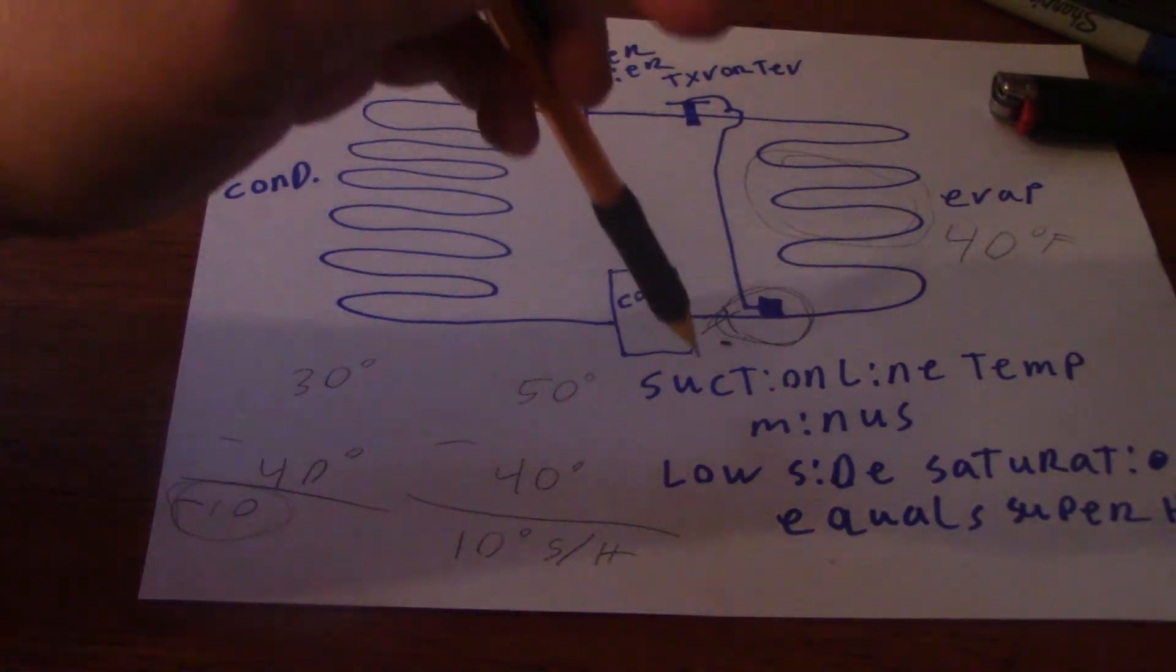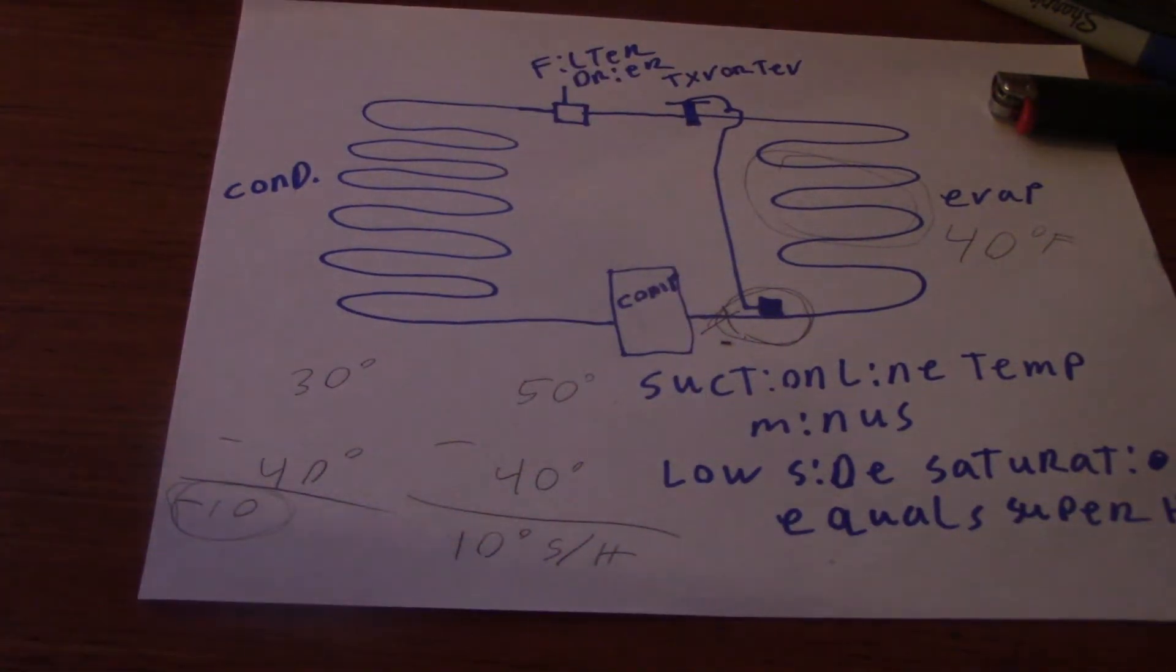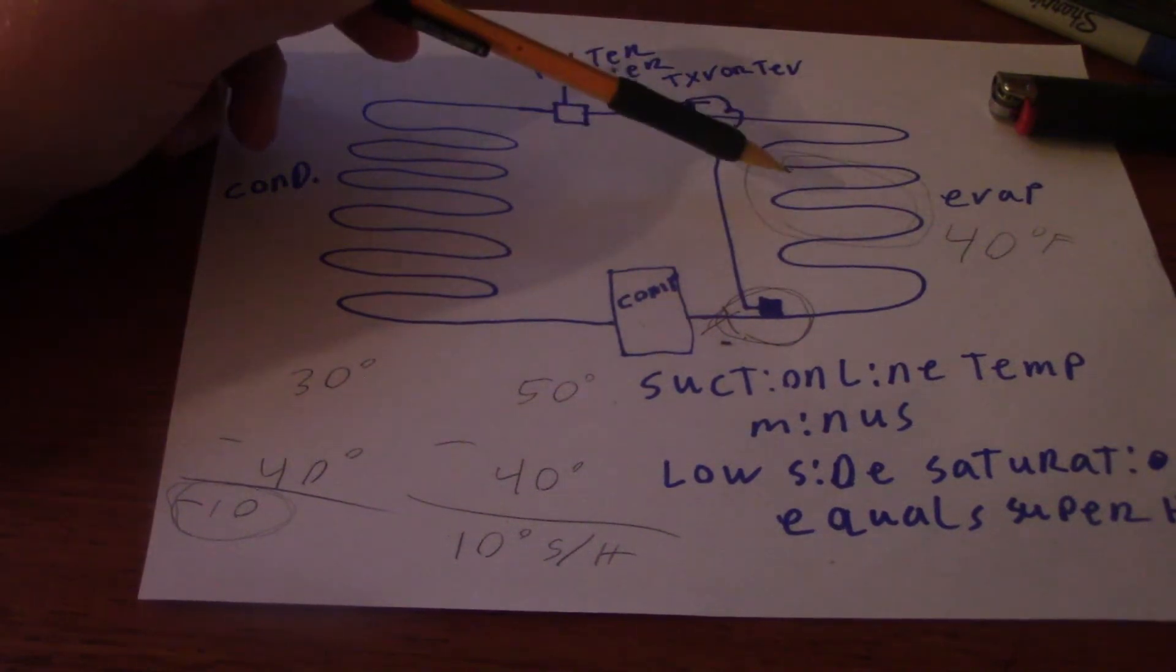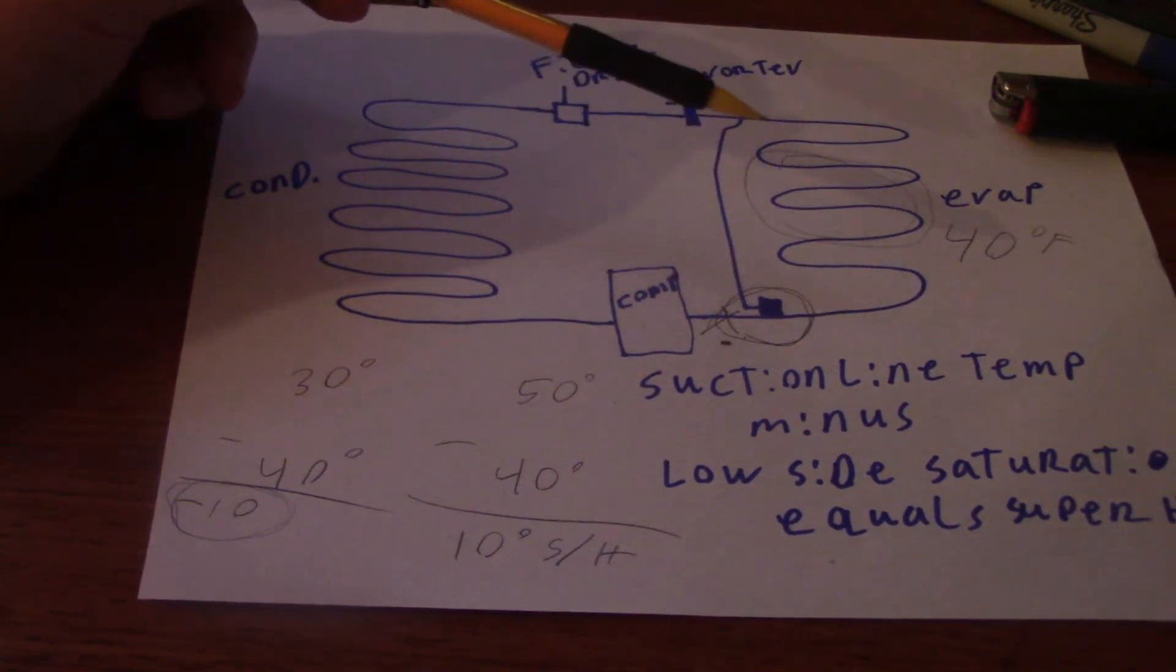So remember, suction line temperature minus low side saturation, because you're trying to pick up how much heat did the evaporator transfer to the refrigerant.